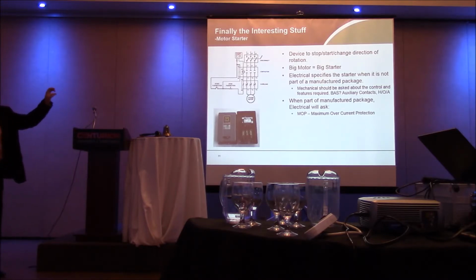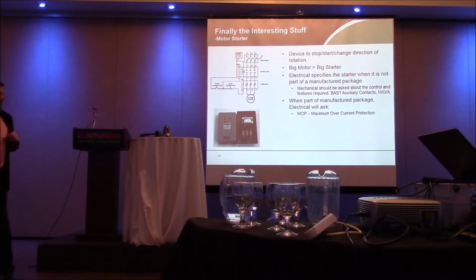When is part of the manufactured package? Electrical is going to ask you some questions. MOP, maximum overcurrent protection, which is basically what the manufacturer says: you have to feed my equipment through a fuse or a breaker of no bigger than this. Again, if electrical's not asking you for that, that's a big red flag, that's a big danger sign.